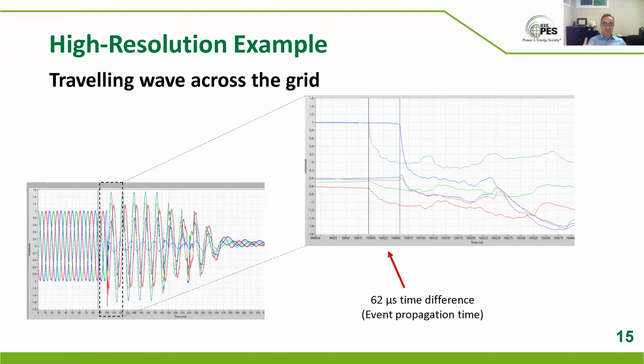This is an application of high resolution synchro waveforms arriving at a central place in this case, or they could just exchange with each other, from the two synchro waveform measurements at the two ends of this line. They're actually really one in each of the substations. This is voltage or electric field based measurement. So all the lines coming to a substation can be monitored with one measurement device.